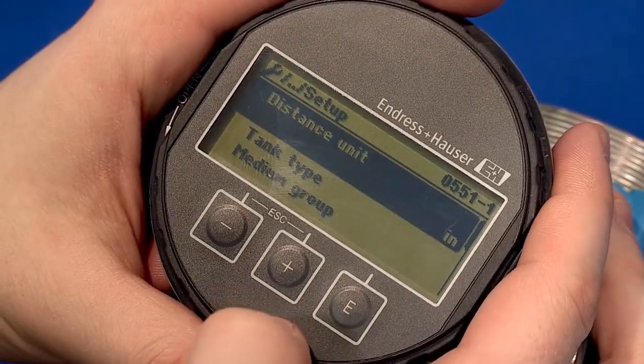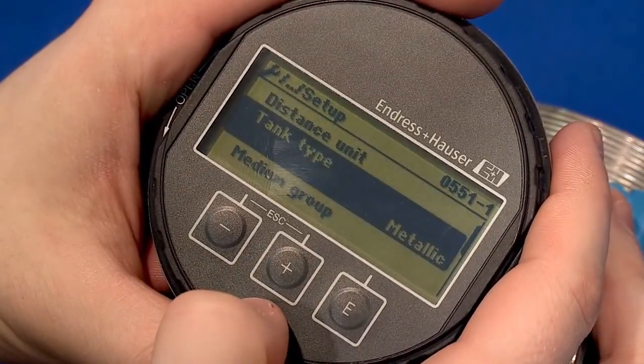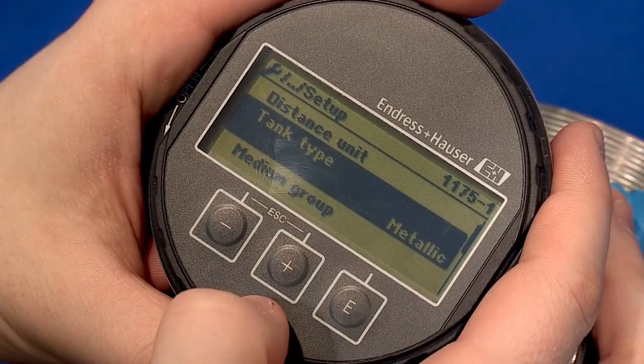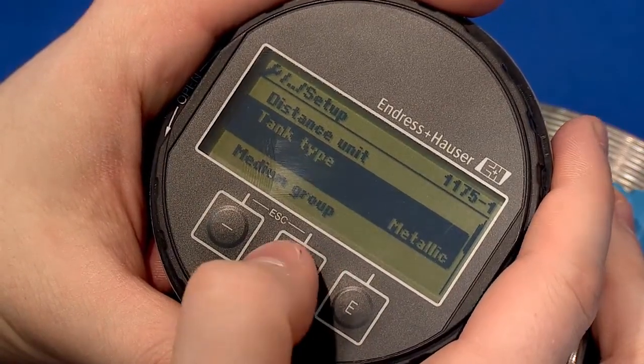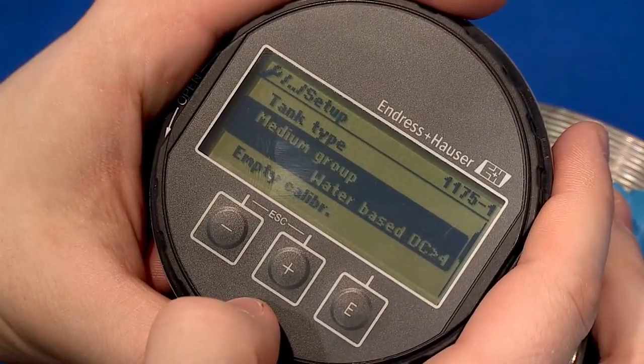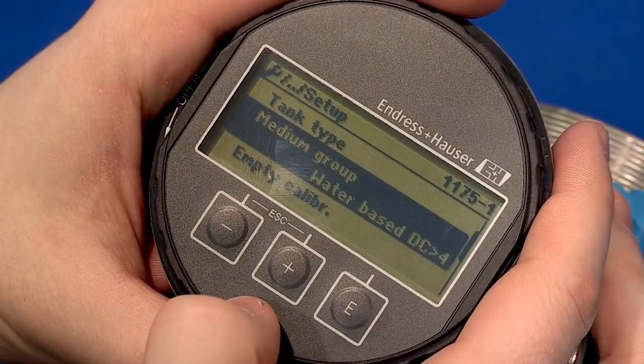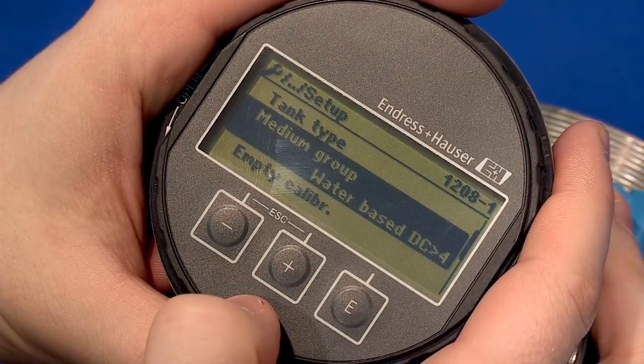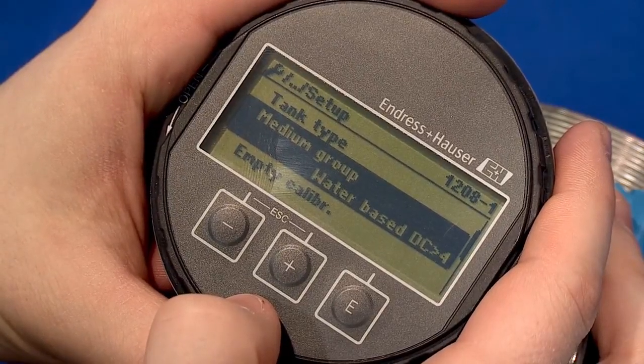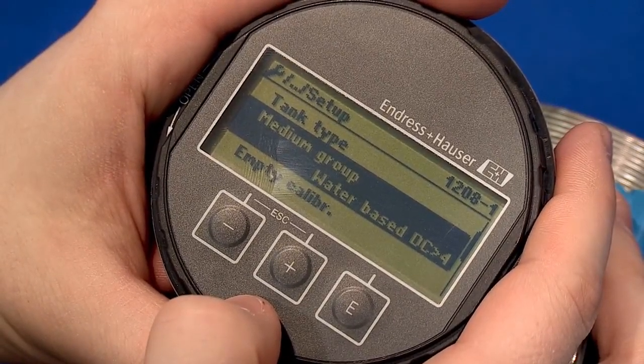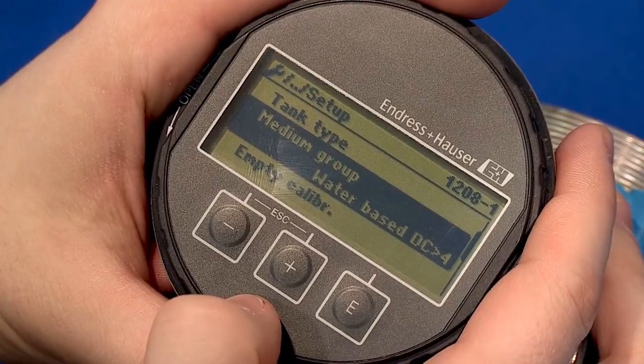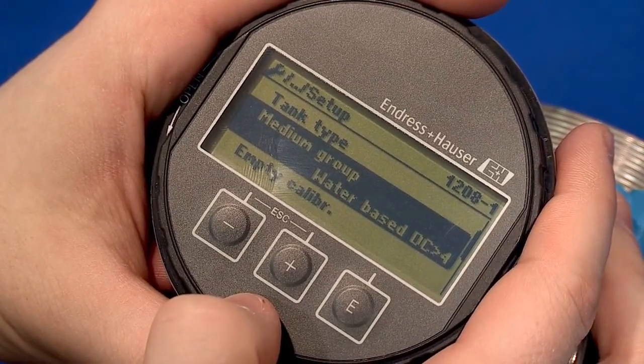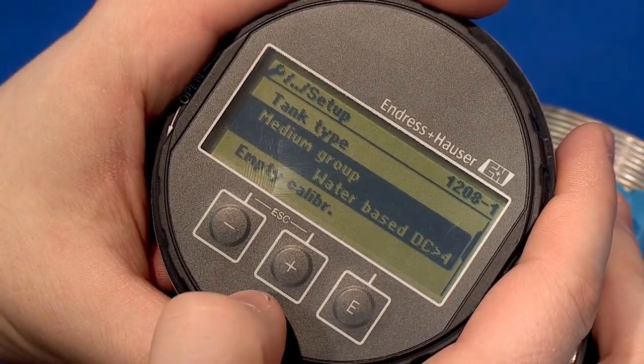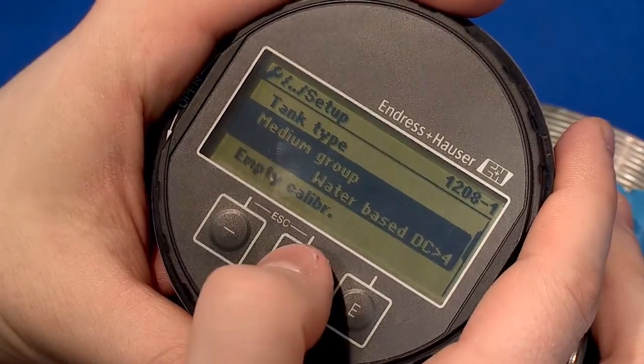The second parameter in the setup is tank type. Select an option that is the best fit for your tank. The third parameter in the setup is medium group. This is related to the dielectric constant of the product. Here you have the option of Others, DC greater than 1.9, or Water-based, DC greater than 4. For our example, we will select DC greater than 4. Once your selection is highlighted, press the plus button.